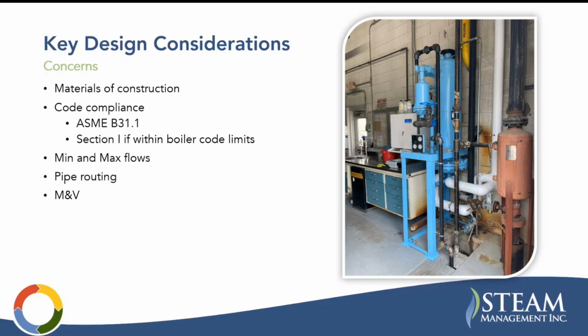Some other concerns: materials of construction. Again, we're talking about code compliance. So if you're in a boiler room with a boiler with decent pressure, you're probably designing to B31.1. You are connecting this system from the boiler, the blowdown line from the boiler to the bottom blowdown tank. You have a steam connection to the deaerator, and then you have makeup water connections. So you have a variety of materials and pipe sizes that you have to run, and you need to worry about your minimum and maximum flow.